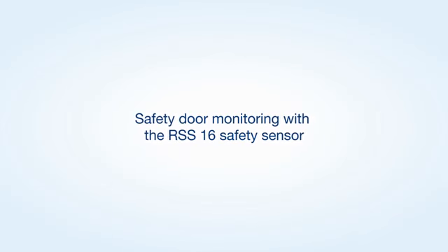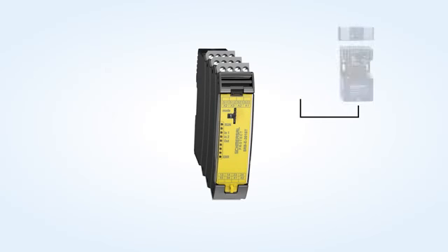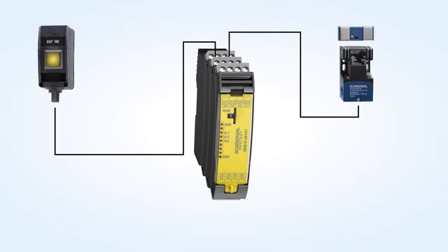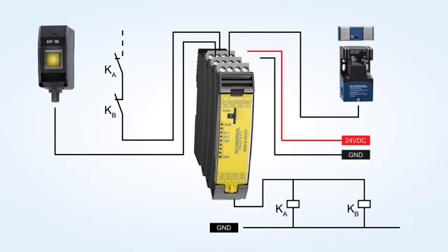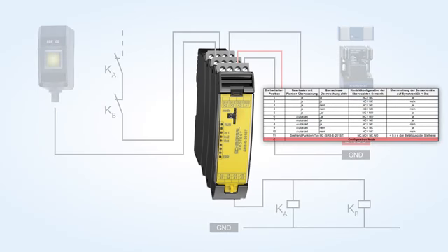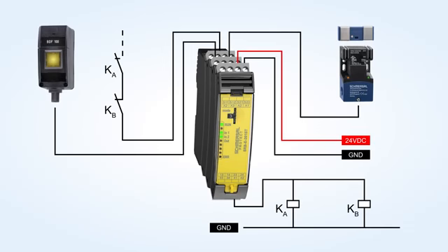Sample application of a safety door monitoring with the RSS16 safety sensor and start button monitoring. The desired application can be simply configured by means of a rotary switch. Formerly saved configurations will be deleted first by turning the rotary switch to position C, configuration mode. Subsequently, set the desired configuration, 1 to 11, using the rotary switch. The system status will be signaled during the setup procedure by means of the LED indications.